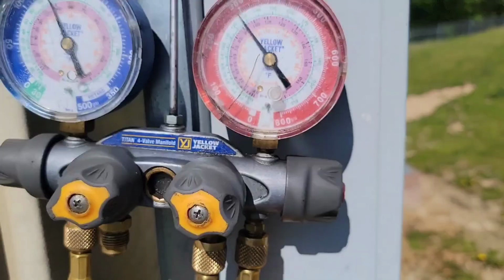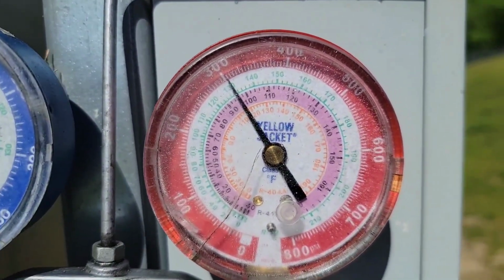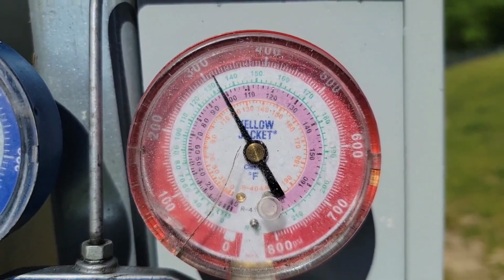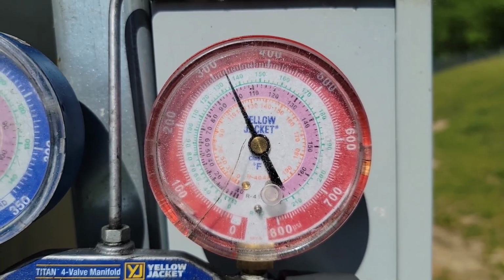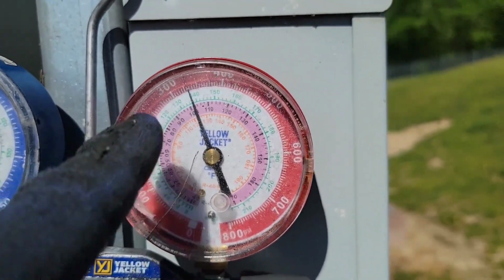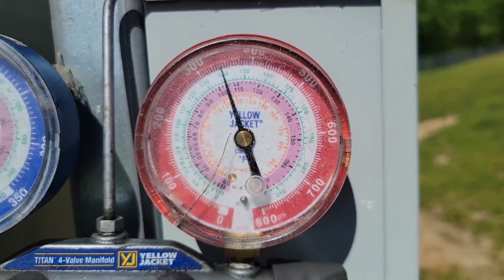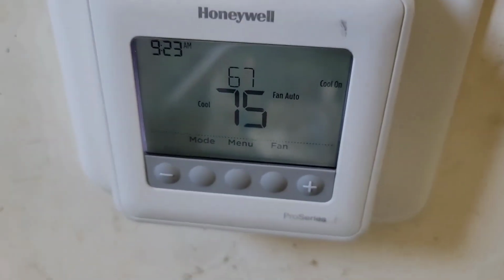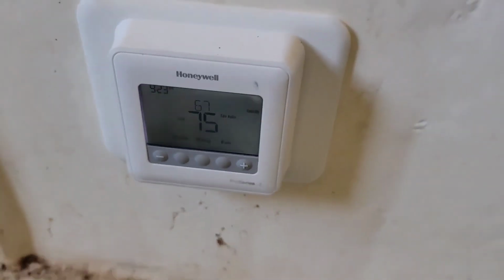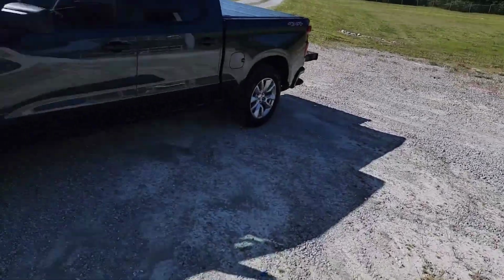We'll check it here in a minute. Look at that head pressure going up. I mean, it's hot in there right now, so I can expect that head pressure to be about 350. Well, it's not too hot. It's only 75 in here right now. But it's early in the morning, so as the day proceeds on, it'll probably become scorching hot in there.